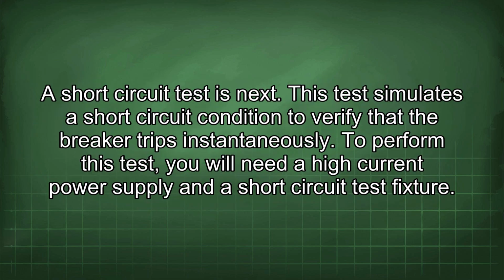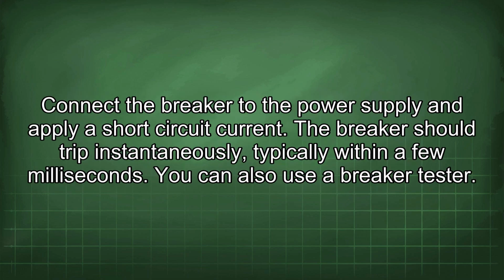A short circuit test is next. This test simulates a short circuit condition to verify that the breaker trips instantaneously. To perform this test, you will need a high current power supply and a short circuit test fixture. Connect the breaker to the power supply and apply a short circuit current. The breaker should trip instantaneously, typically within a few milliseconds.